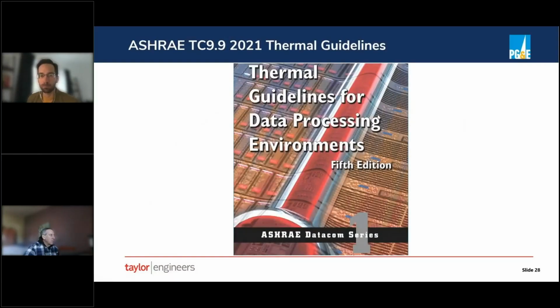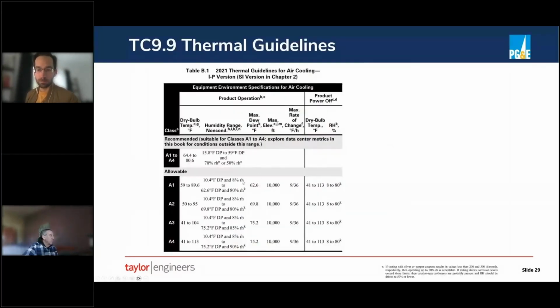ASHRAE has a technical committee called Technical Committee 9.9, and they put out a set of thermal guidelines that is the de facto industry standard for those environmental conditions. And in this guideline, there are a set of criteria for things like dry bulb temperature, humidity, maximum dew point, maximum rate of change for different classes, if you will, of computers. There's what's called the recommended criteria, and then there's allowable for A1 class, A2, A3, and A4. And the recommended are the tightest in terms of things like the dry bulb and the humidity, and the allowable get wider and wider.